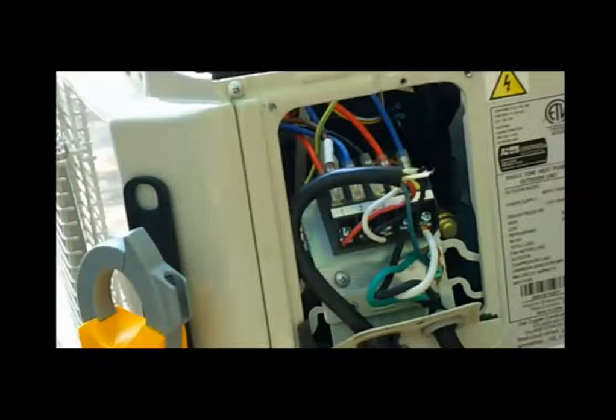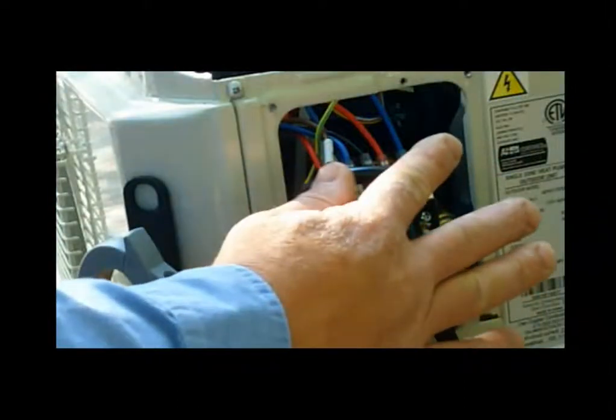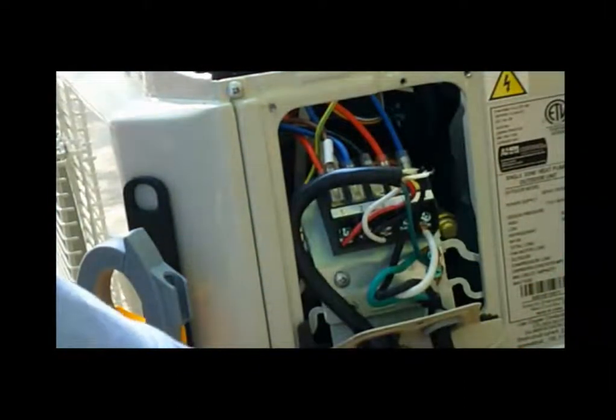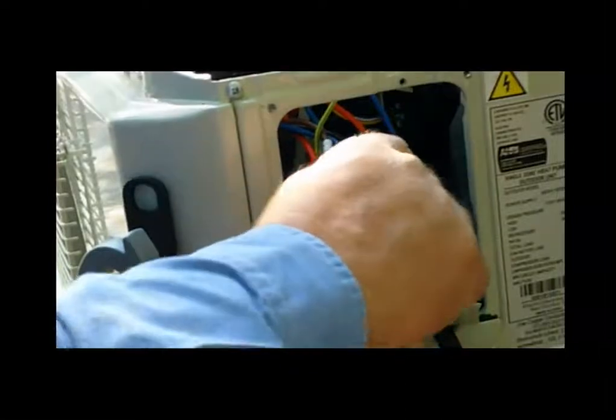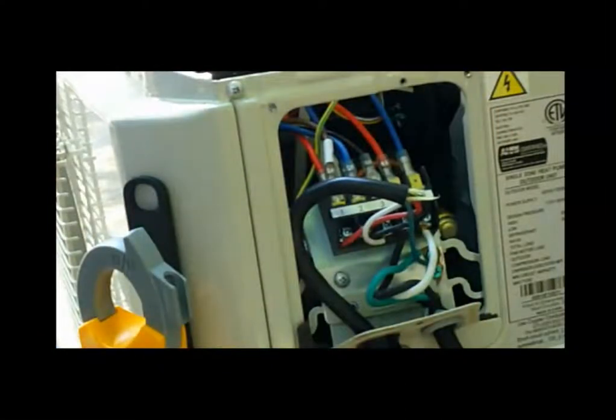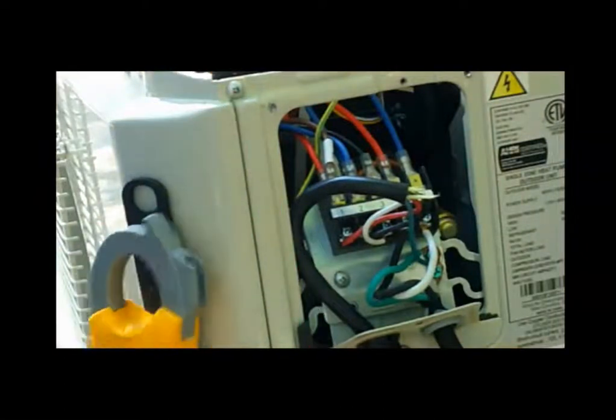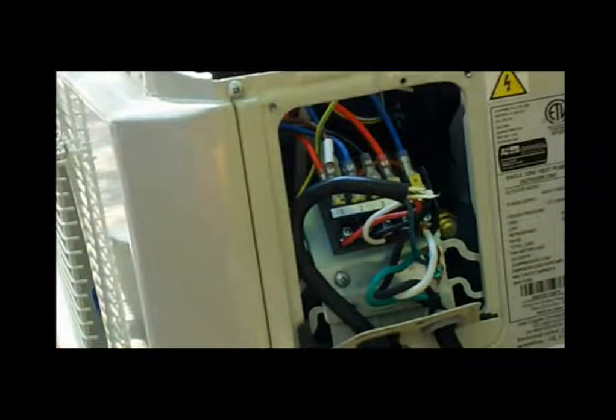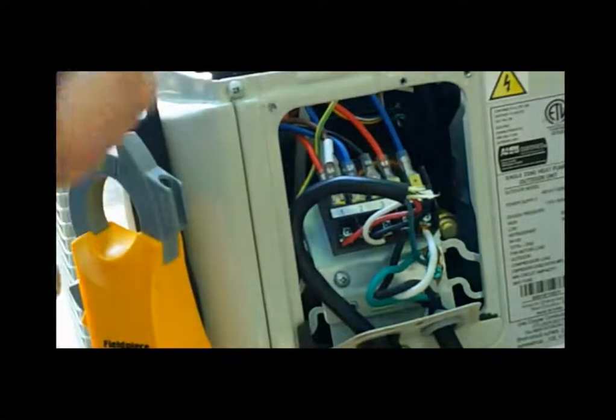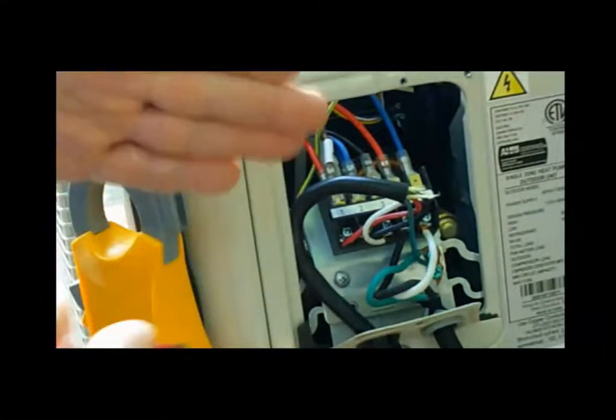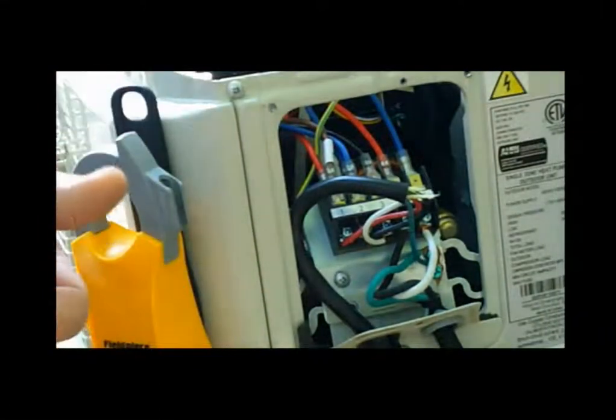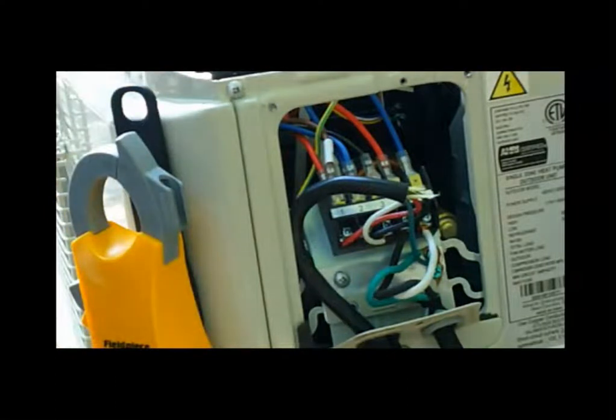Okay, now that we've got the power back on, we are in standby mode. As you can tell, we've got this access here. So what we need to do is trace the power wires that come in. We're going to note that on my system it's 115 volts. So we're going to go line to neutral and check the AC voltage and make note of that. Now, be very careful because we are live on this unit, so we do have high voltage AC and high voltage DC within this power.